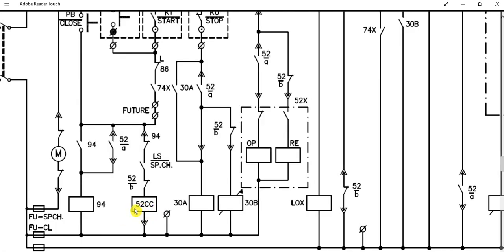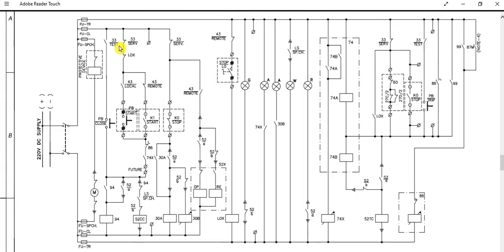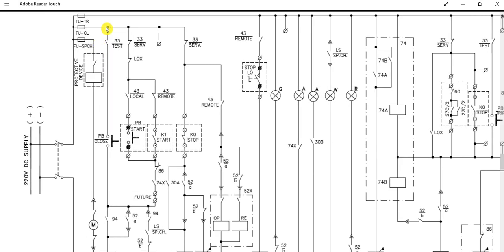For the closing circuit, there is a closing coil inside the breaker — 52CC is the circuit breaker closing coil. We need to energize this coil to get the breaker closed. Suppose the breaker is in test position — if the circuit breaker is in test position, this contact will be closed.